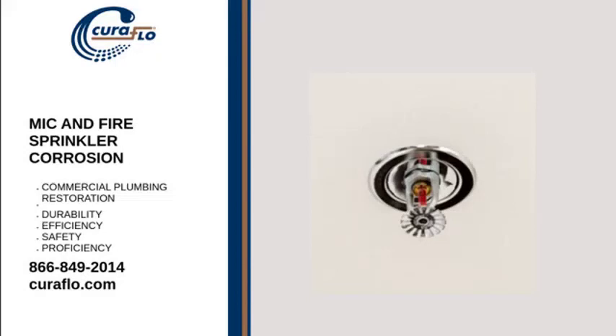Two types of premature failure commonly occur. The first is the system failing to hold water, which is caused by pinhole leaks from the accelerated, localized corrosion. This can cause significant system damage and may result in water damage. The second type of failure prevents the system from operating as designed to achieve fire control due to biological growth.